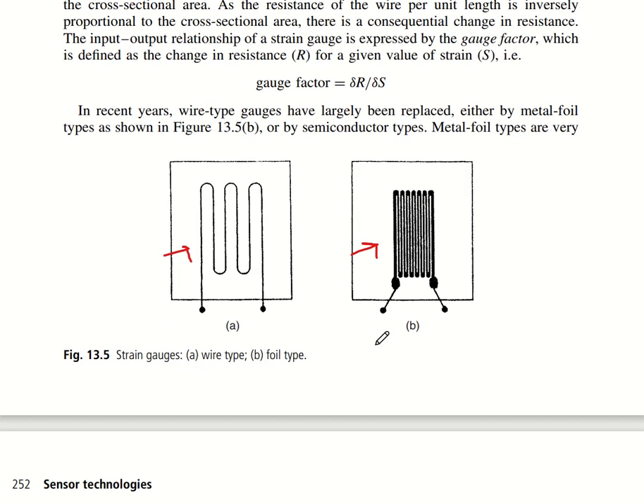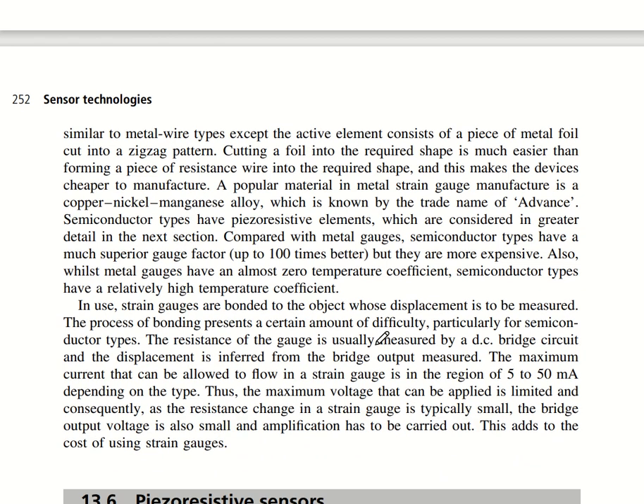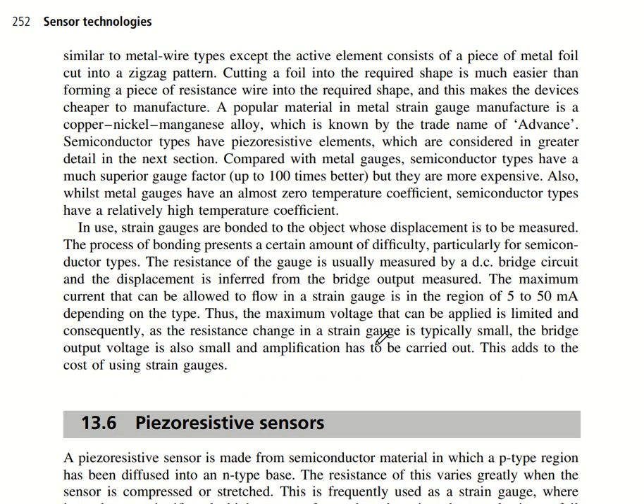Metal foil types are very similar to wire types except the active element is a piece of metal foil cut into a zigzag pattern. Cutting foil into the required shape is much easier and cheaper to manufacture than forming resistance wire. Strain gauges are made of copper-nickel-manganese alloys known by the trade name Advance. Semiconductor types have a piezoresistive element with a gauge factor up to around 100 times better than metal gauges, but they are very expensive.